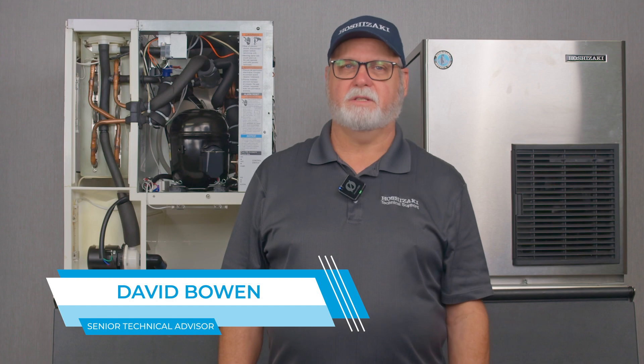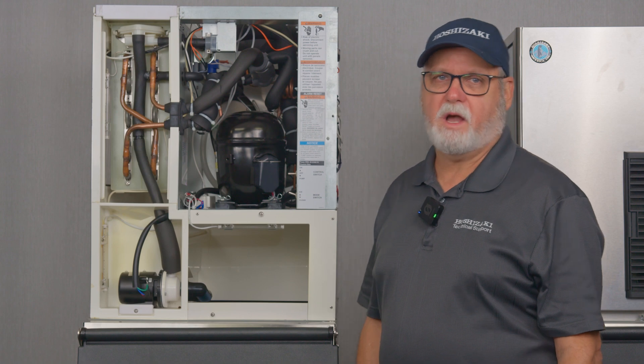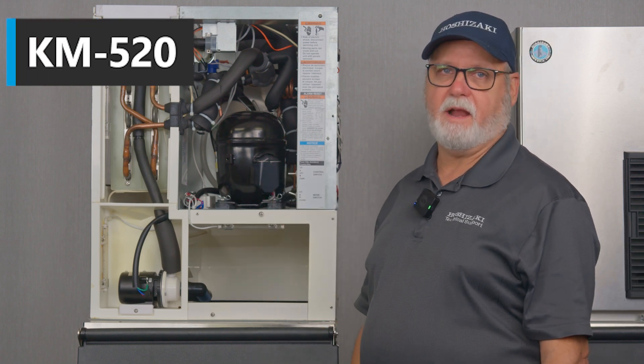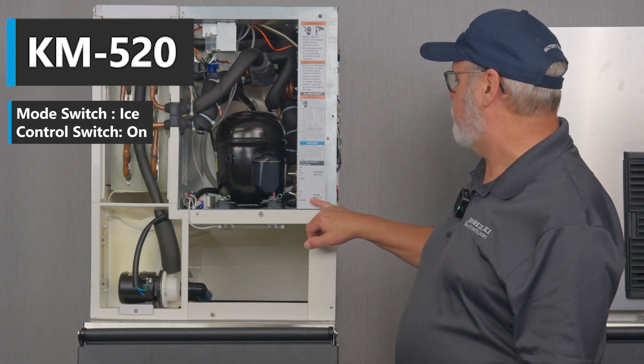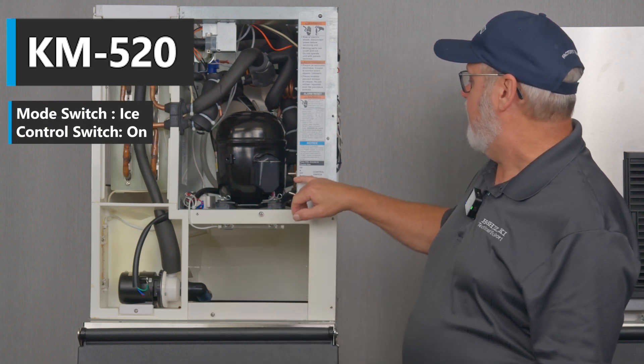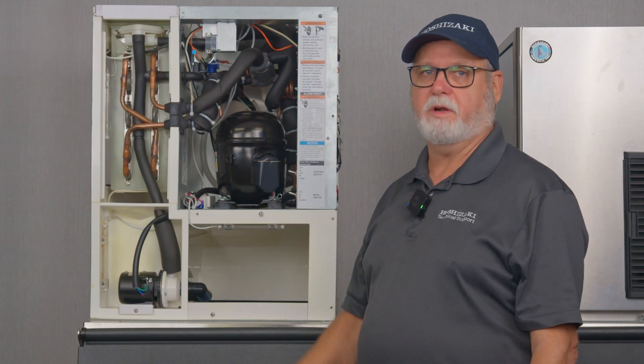Welcome to Hoshizaki Technical Training. I'm David Bowen, here to talk to you today about sequence of operation on the KM ice machines. Today we're going to be talking about a KM 520 self-contained air-cooled machine. To get this machine started you need to make sure your mode switch is in ice position and your control switch is in the on position to get the unit started in the fill cycle.